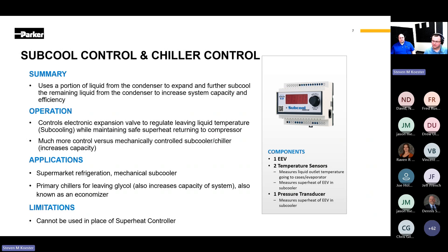So if you set the low temperature cutoff to 30, when the liquid out temperature reaches 30 degrees, the chiller control will close the EEV and turn off refrigeration. The subcool control is commonly used with low temperature supermarket rack systems. The chiller control is designed for use on primary chillers for secondary coolants, such as glycol systems in supermarkets and commercial buildings. Although these controllers maintain superheat, it is not recommended to use either in place of a superheat controller.